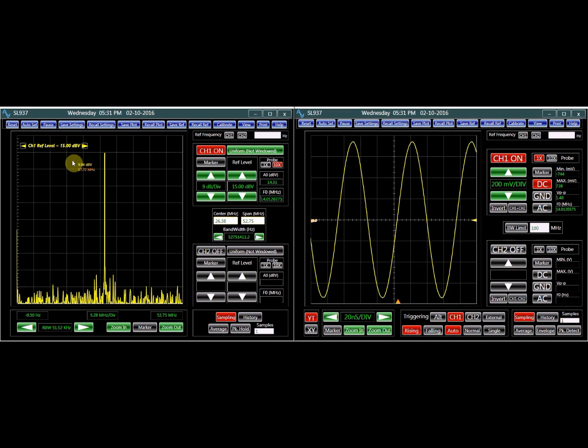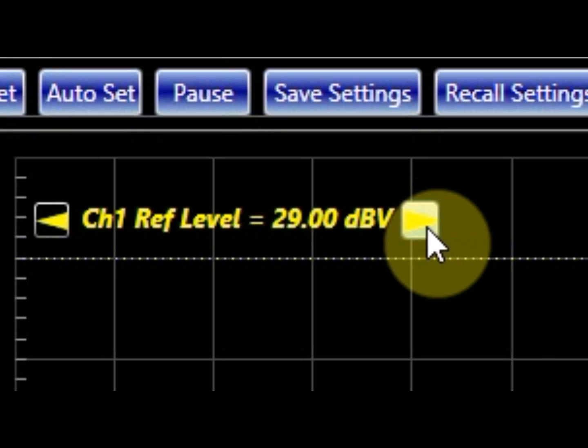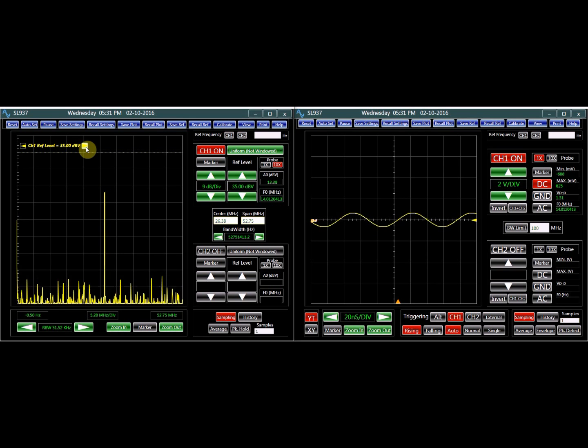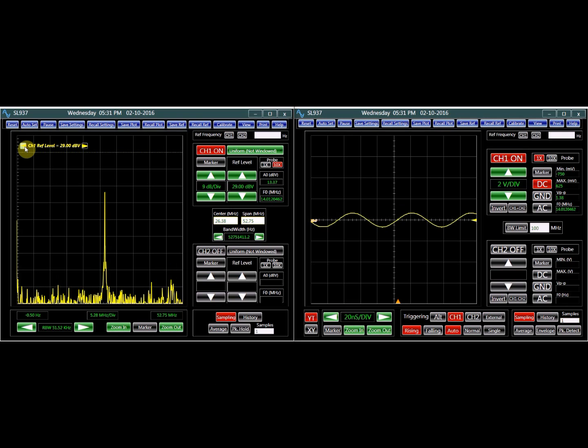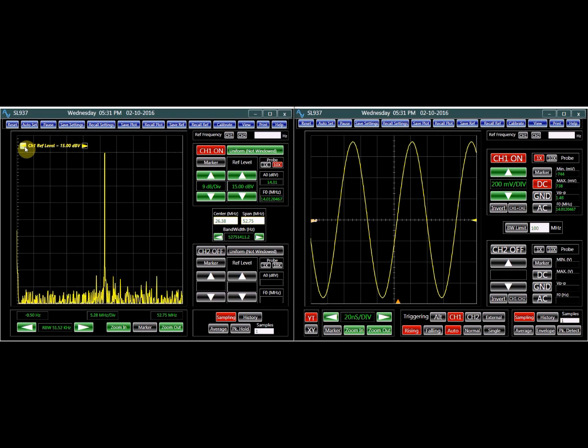The reference level should be set for the highest dynamic range for the signal under test. If we set it too high, we lose some of the dynamic range, making it harder to detect smaller components of the signal. And if we set it too low, we lose some of the signal as it clips out of the range of the spectrum analyzer.